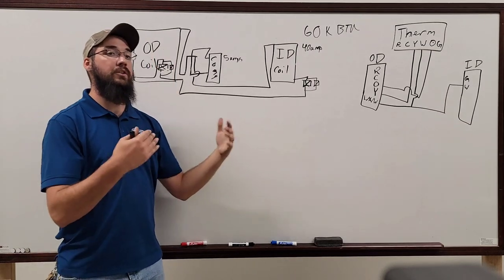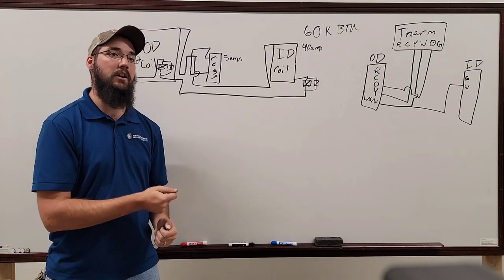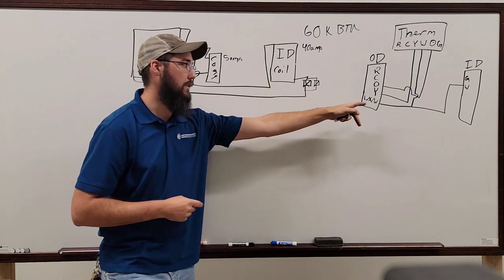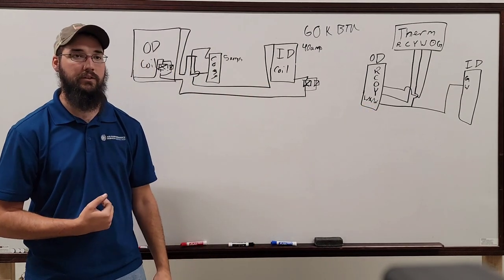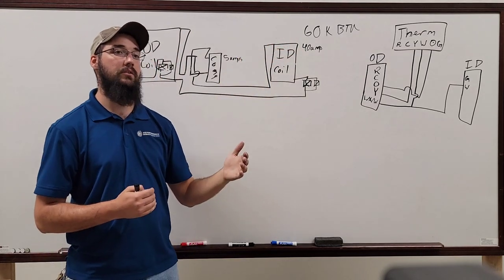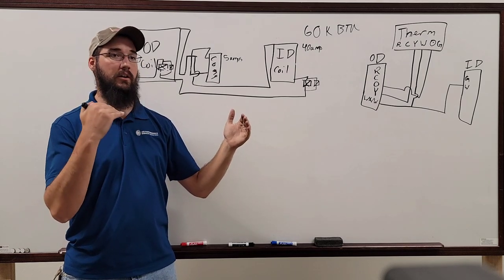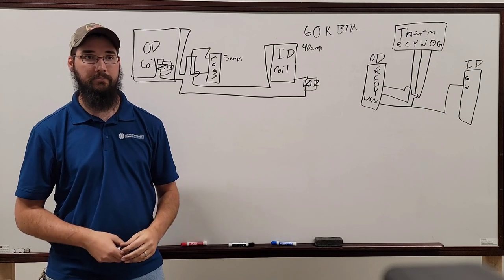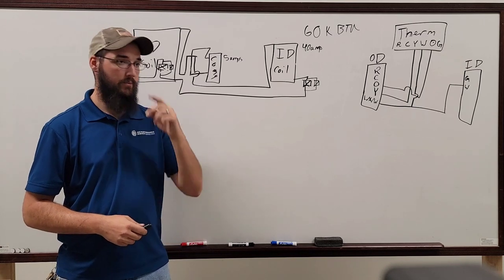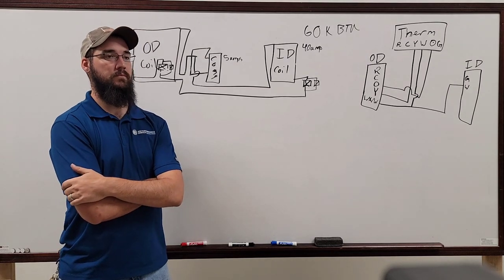Now, again, many modern systems will see that once the coil temperature gets back above a certain temperature, it will automatically come out of defrost, cycle back over to heating mode, and it will kill the W signal and turn the auxiliary heat back off. So the whole time you're in defrost, your auxiliary heat's primary function is to mitigate the cooling effect that's happening from what's now become the evaporator again. Okay? So if your fan's not running on a frozen coil, you're in defrost. Yes. And if your fan's not running and you're trying to heat outside, something's wrong.